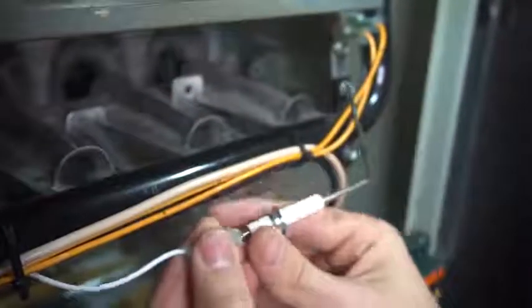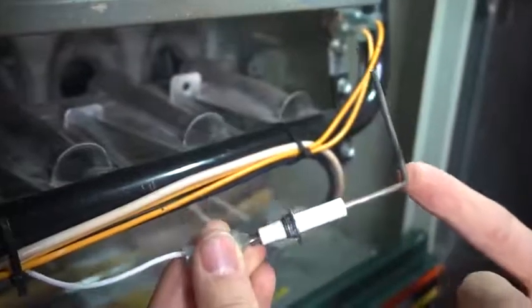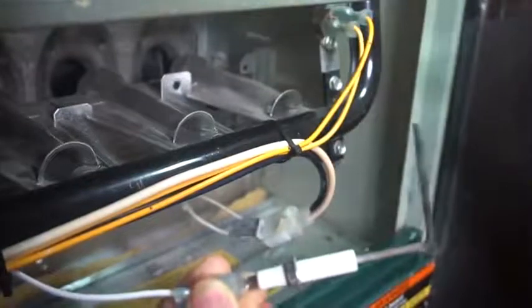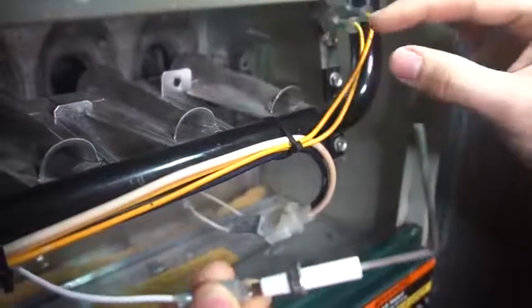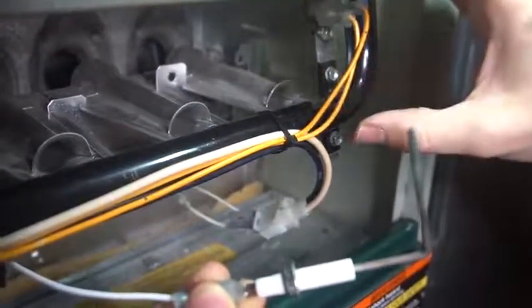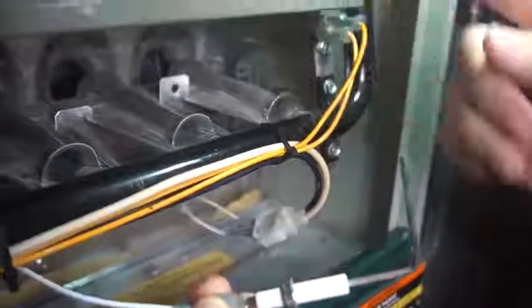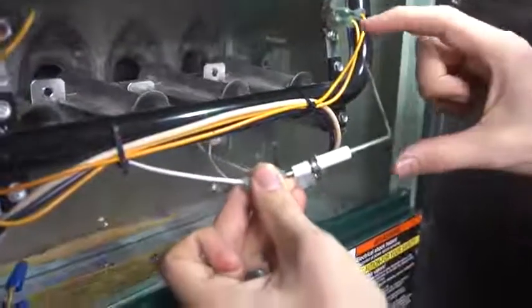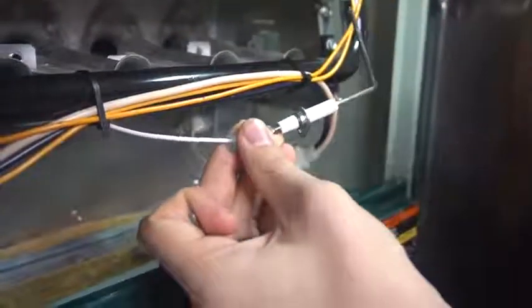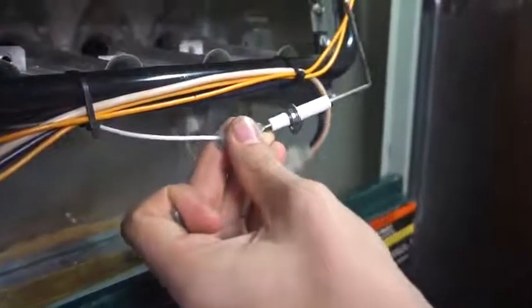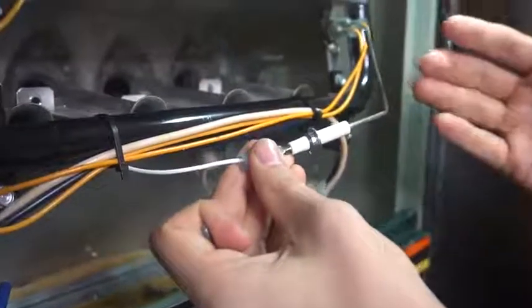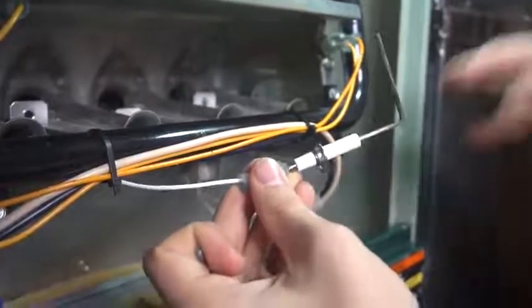And the purpose of this flame sensor, it's another safety device. The purpose of it is to basically turn off the gas if the igniter fails. So for example, if the igniter for some reason burnt out, or for some other reason it's not glowing or not sparking to ignite the gas, the valve will still open and allow gas to go through. But if there's no flame, this flame sensor is there to shut off the gas so you don't just have gas spewing out. But at the same time, when this flame rod gets dirty enough, it tricks the furnace into thinking that there's no flames, and it shuts the burners off.